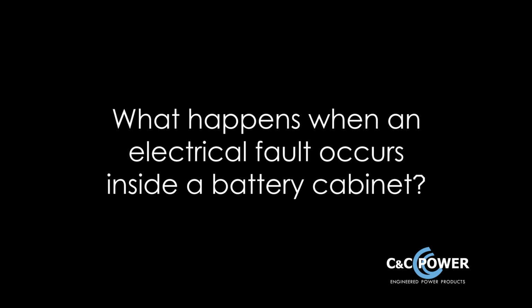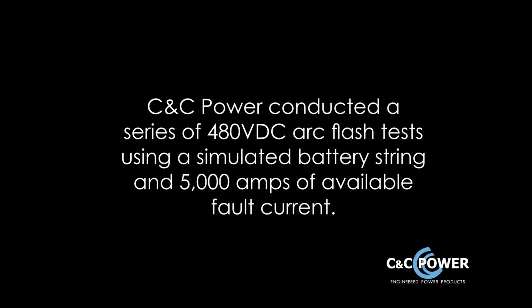What happens when an electrical fault occurs inside a battery cabinet? To find out, C&C Power conducted a series of 480 VDC arc flash tests using a simulated battery string and 5,000 amps of available fault current. High-speed cameras and calorimeters were used to capture and measure the resulting events.